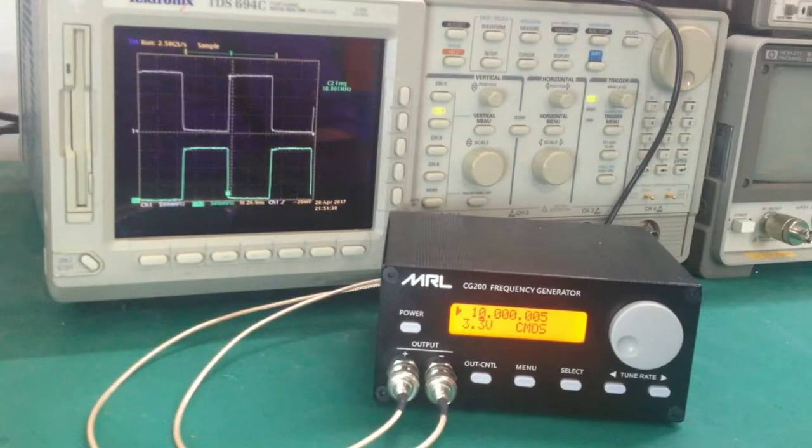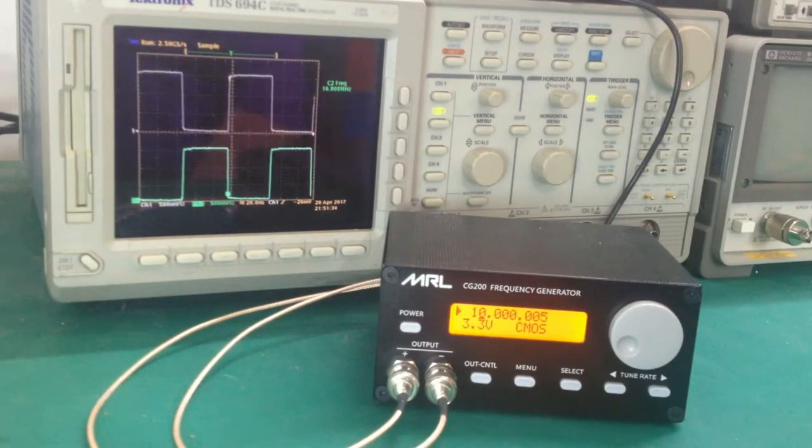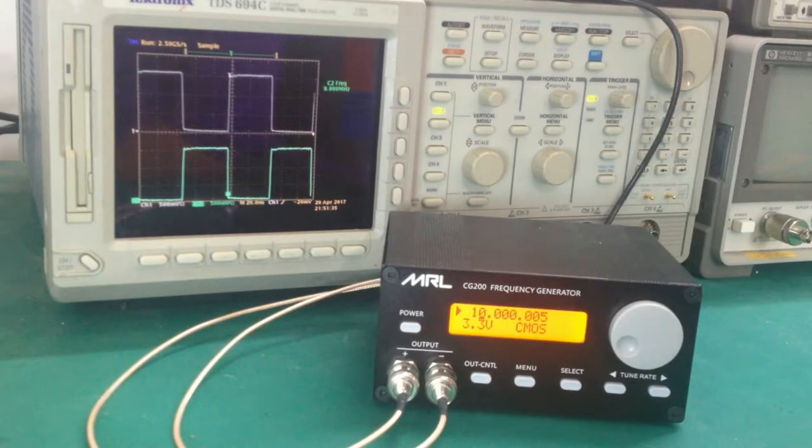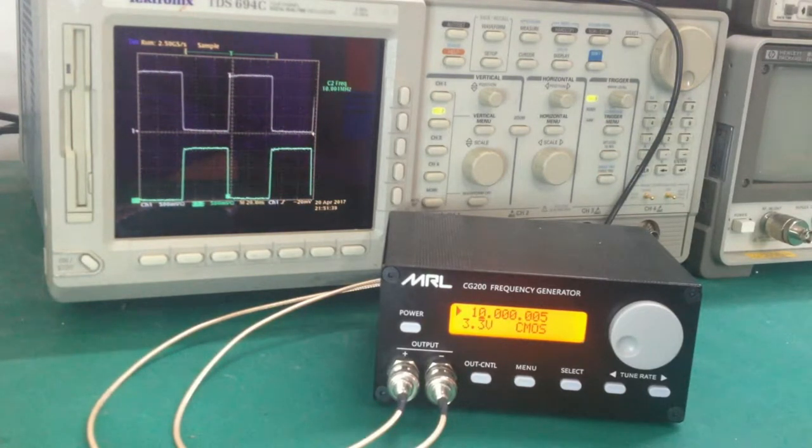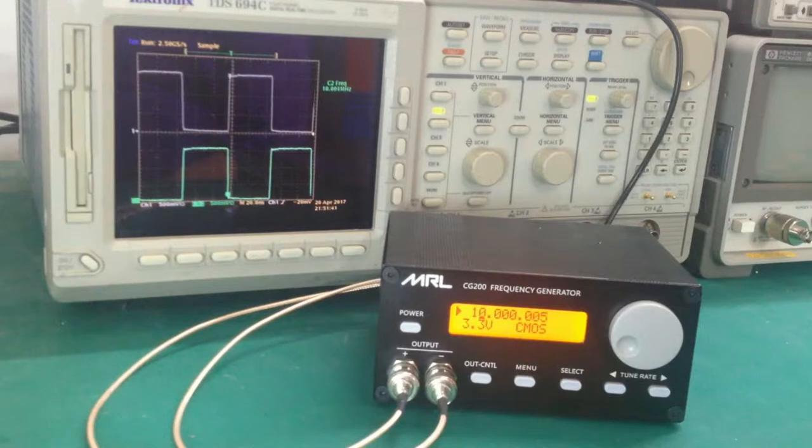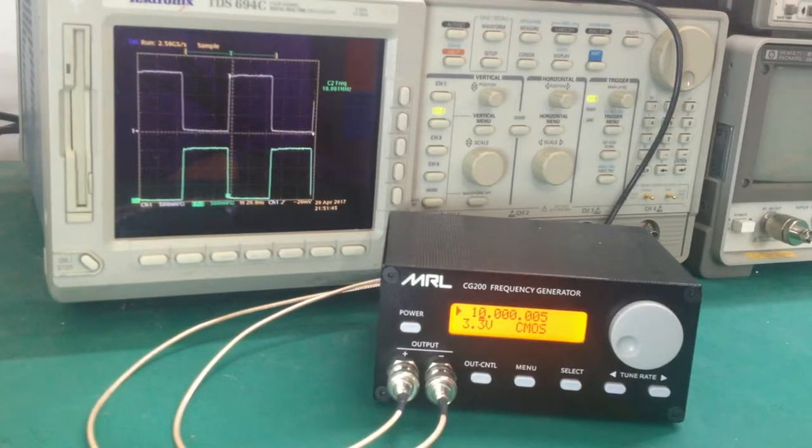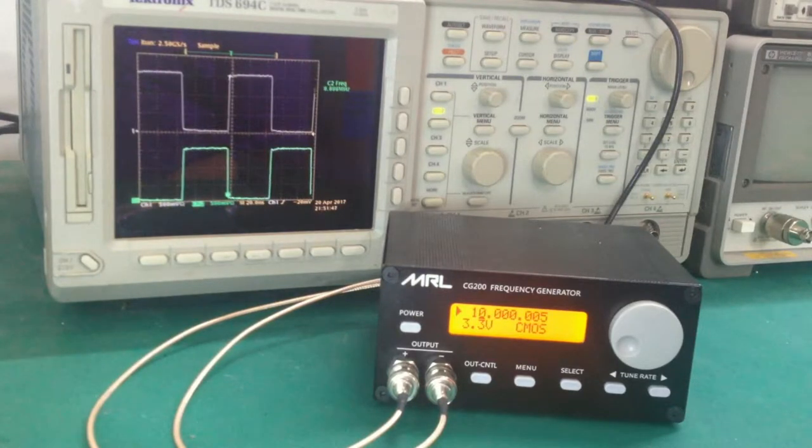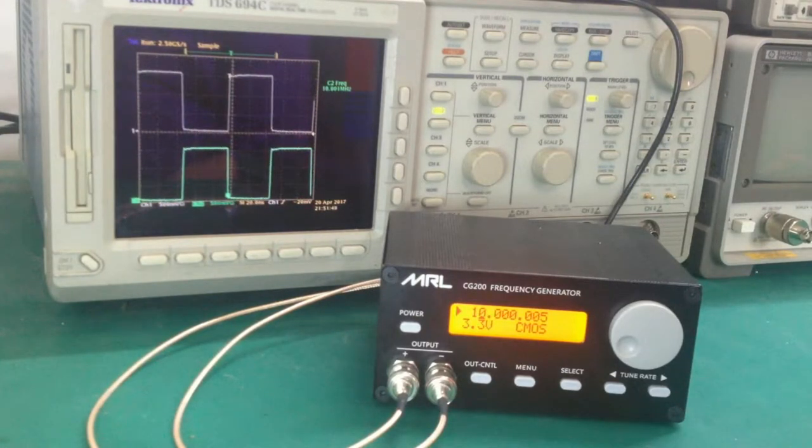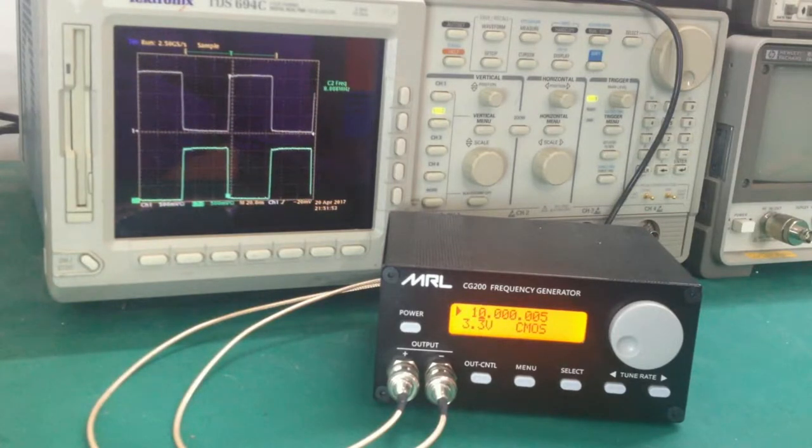There are two modes that this initial state can be for the CG200. It can be programmed either to come up as the last settings used, or it can come up in a pre-programmed set of frequency, voltage, and logic type. Each time you turn it on, you want it to always come up in a particular mode regardless of how it was last used. But here it is, coming up in the factory default mode.